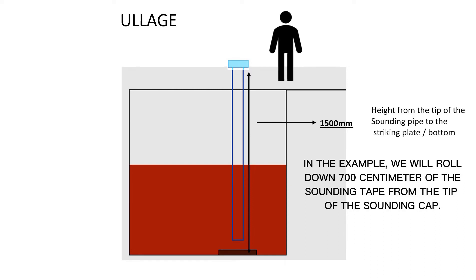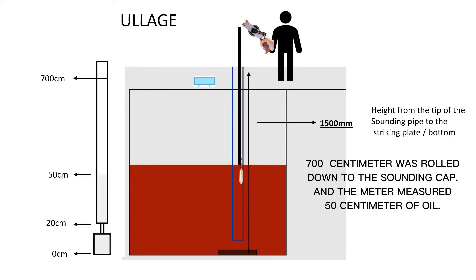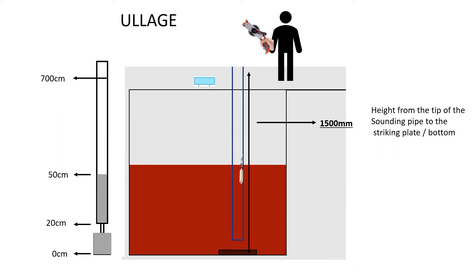In the example, we will roll down 700 cm of the sounding tape from the tip of the sounding cap. 700 cm was rolled down to the sounding cap, and the meter measured 50 cm of oil.